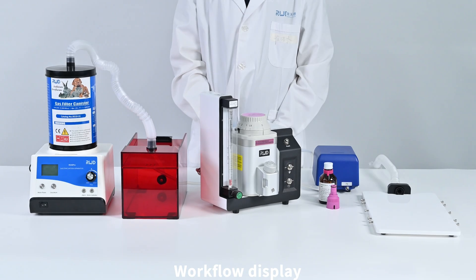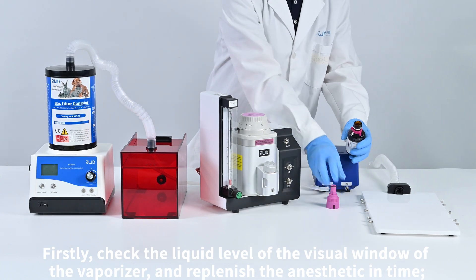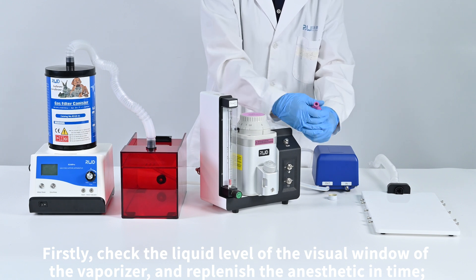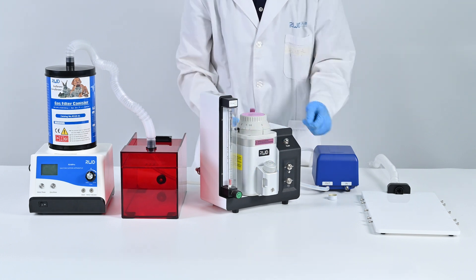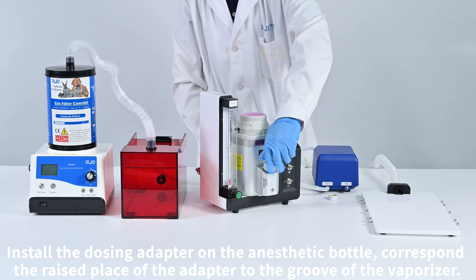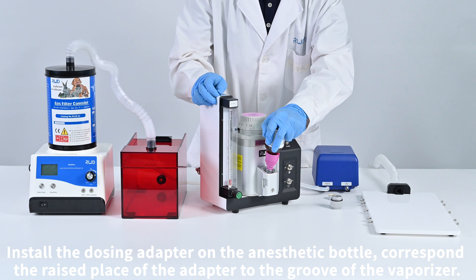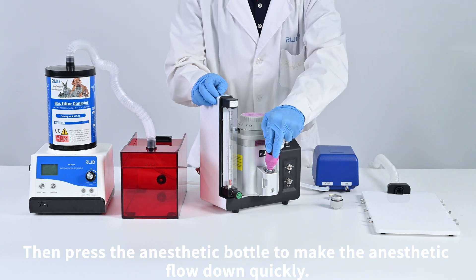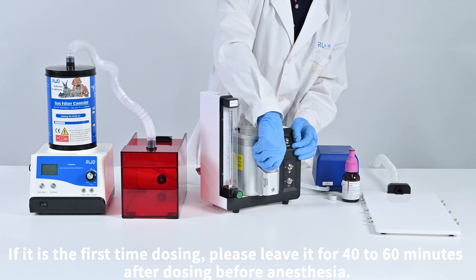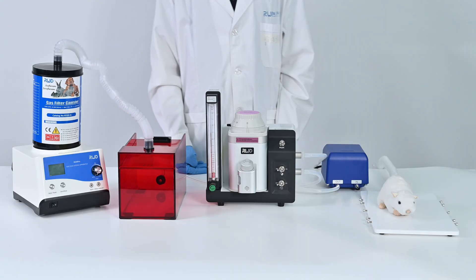Workflow display. First, check the liquid level of the visual window of the vaporizer and replenish the anesthetic in time. Install the dosing adapter on the anesthetic bottle, aligning the raised part of the adapter to the groove of the vaporizer, then press the anesthetic bottle to make the anesthetic flow down quickly. If it is the first time filling, please wait 40 to 60 minutes after filling before beginning anesthesia.